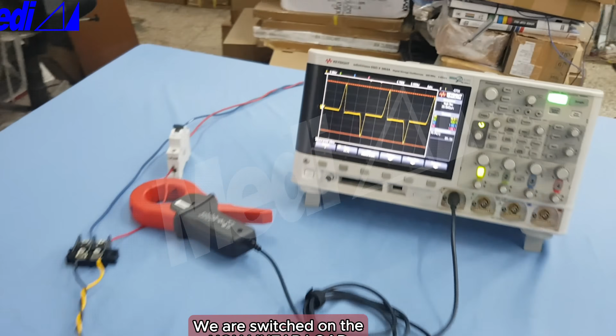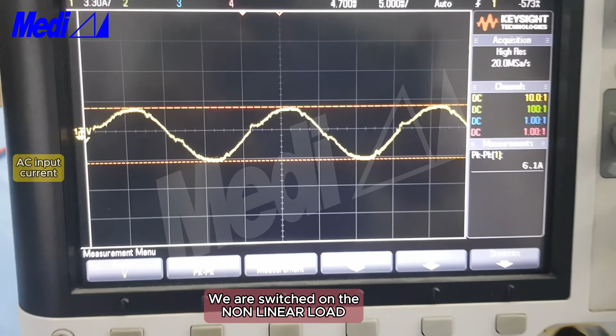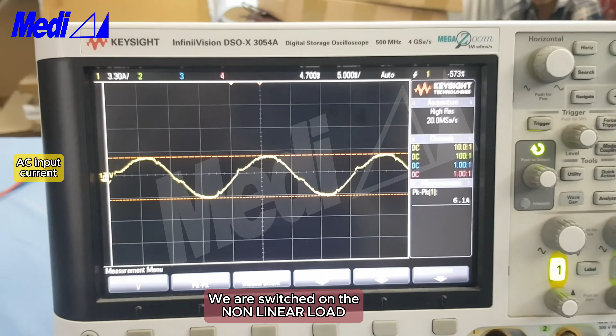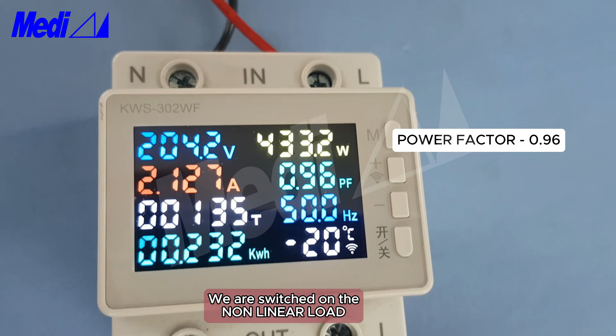Now let us switch the current clamp meter to the input. You can see the current came down. It's only 6.1 ampere. The power factor has improved and current harmonics has come down. The power factor has improved to 0.95, while the harmonics has reduced to 3%.